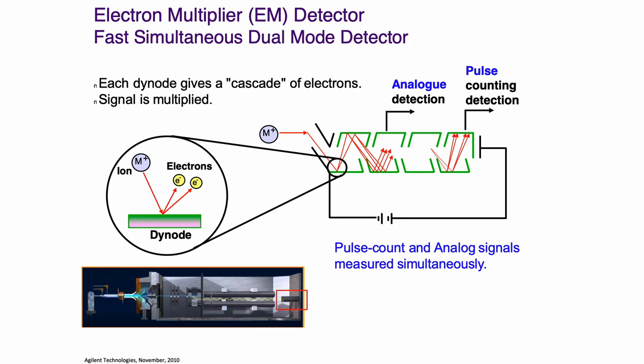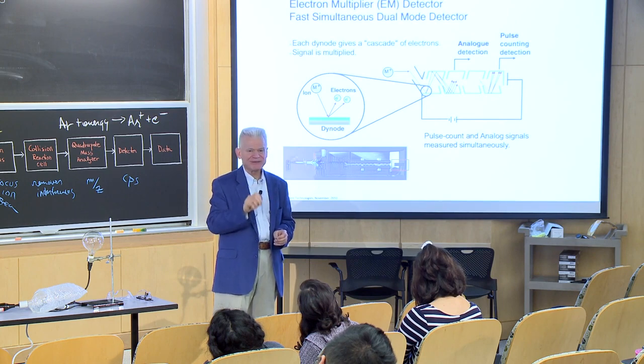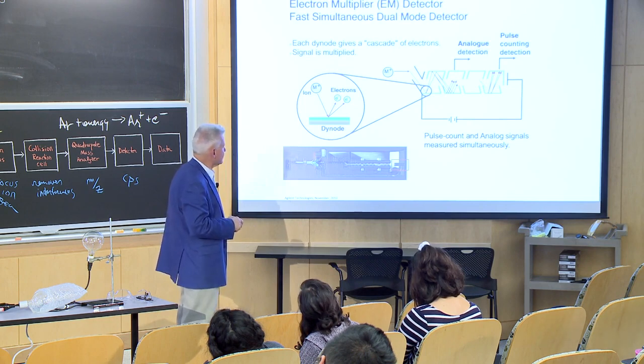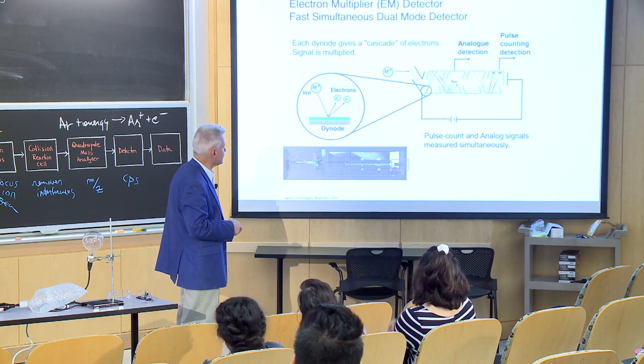So it goes back a few dynodes, picks up the analog signal, and then the software multiplies that by some pulse analog ratio to make it look like a pulse. It's quite complex, but you can actually, when it's graphing your elements, if a point goes on the graph, you can tell whether it's a pulse or analog point, and if it's been corrected. So this is pretty much the detector. Let's see what else we have here.